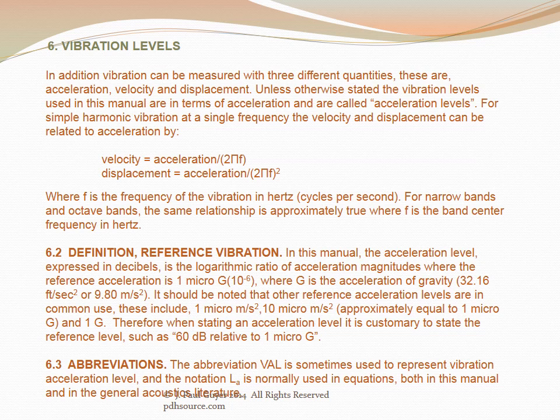For simple harmonic vibration at a single frequency, velocity and displacement can be related to acceleration by: velocity = acceleration/(2πf), and displacement = acceleration/(2πf)², where f is the frequency in hertz. The same relationship approximately holds for narrow and octave bands using the band center frequency. The acceleration level in dB uses a reference of 1 micro-g (10⁻⁶ g), where g = 32.16 ft/s². The abbreviation VAL or L_A is used for vibration acceleration level.